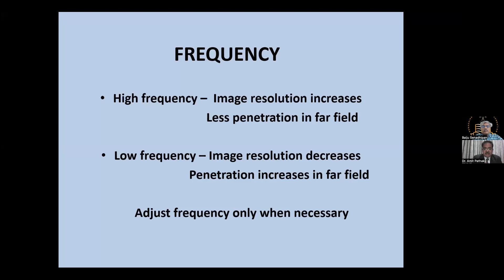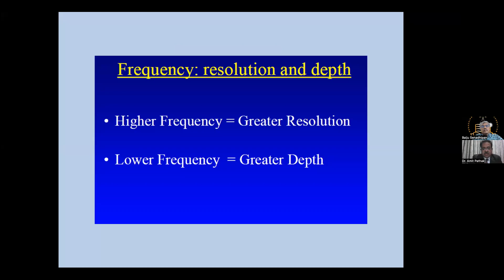Whereas when we have to do transabdominal ultrasound, we have to put the probe over the surface of the patient's body, then obviously we want the ultrasound to penetrate the whole body from the anterior abdominal wall to the posterior abdominal wall. And for this, we do use low frequencies, but there the disadvantage comes in that the image resolution decreases. So a lot of times we mix transabdominal and endoscopic ultrasound to get the best analysis. One has the advantage of depth, the other has the advantage of resolution. High frequency, greater resolution; lower frequency, greater depth. This is the basic principle of ultrasound.